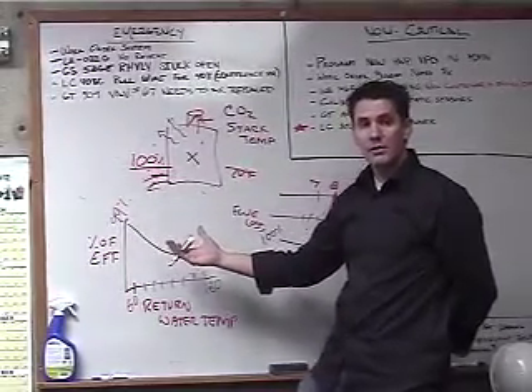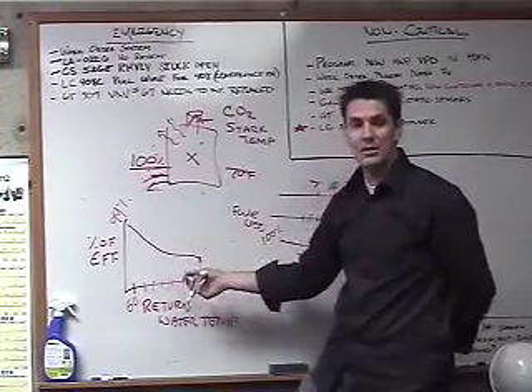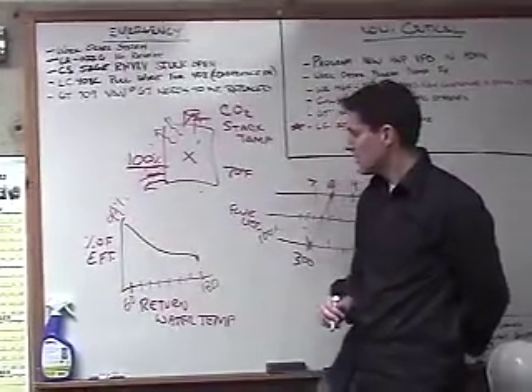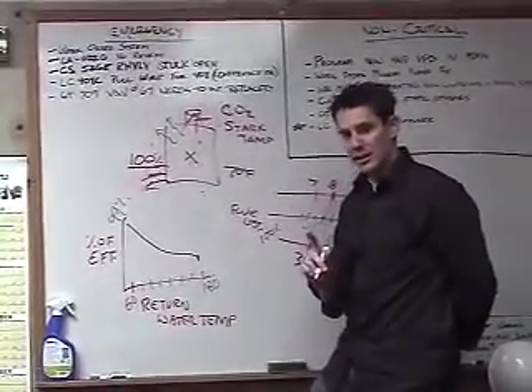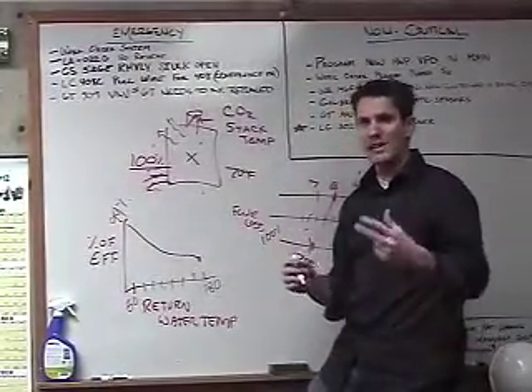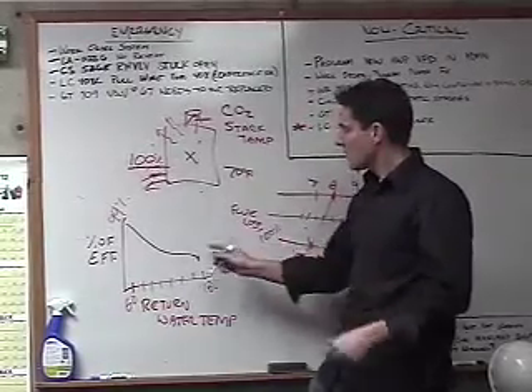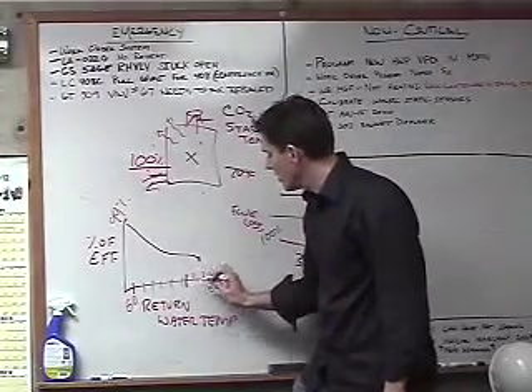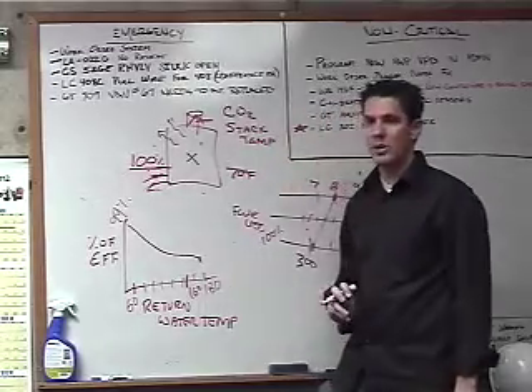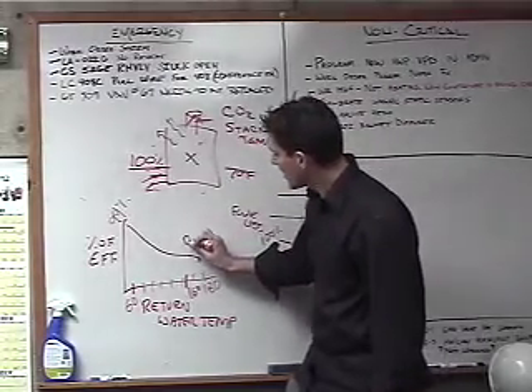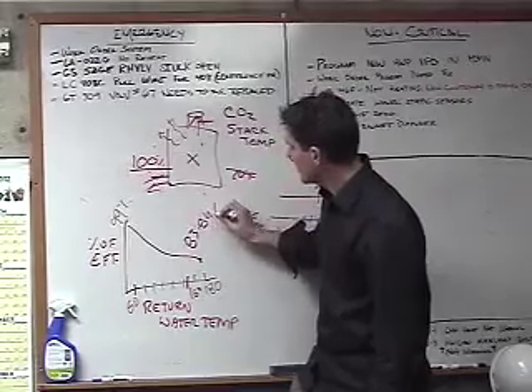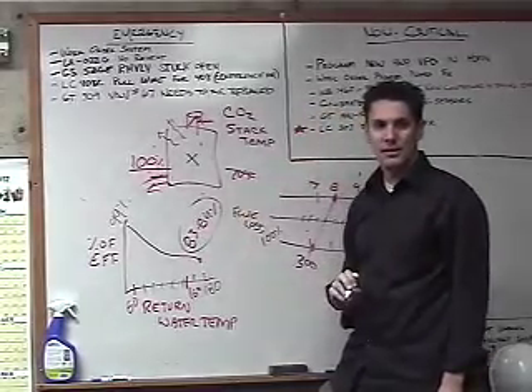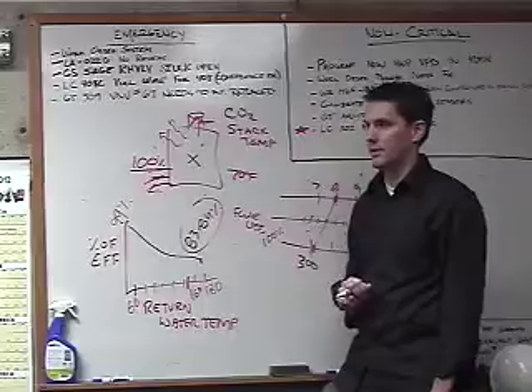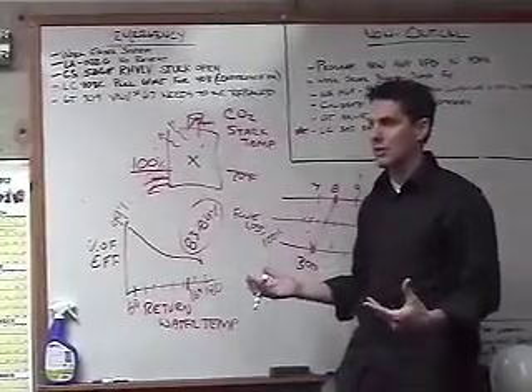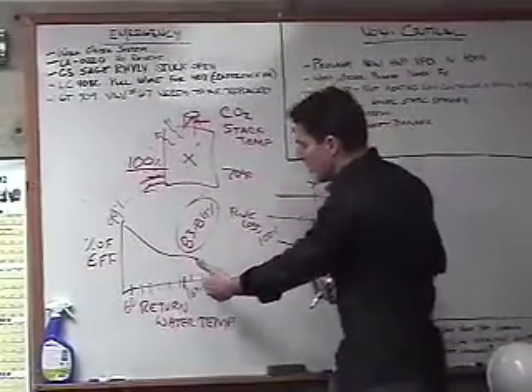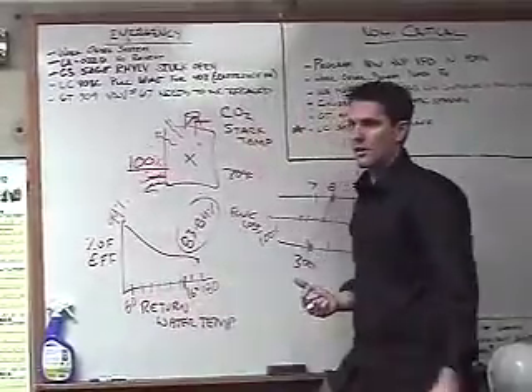If you do snow melt, you can have temperatures that are around 90 degrees, 100 degrees, so you're going to be somewhat efficient. When I got to Boise, almost every job, this is why I asked the engineers this question, almost every job that they were putting these boilers in, they were coming back with 160, and they're heating the water up to 180. Their boilers were operating at 83 to 84% efficient at best, just like any other boiler would, because it goes back to the whole process of combustion. It doesn't matter. So why? Why am I more efficient with colder water?